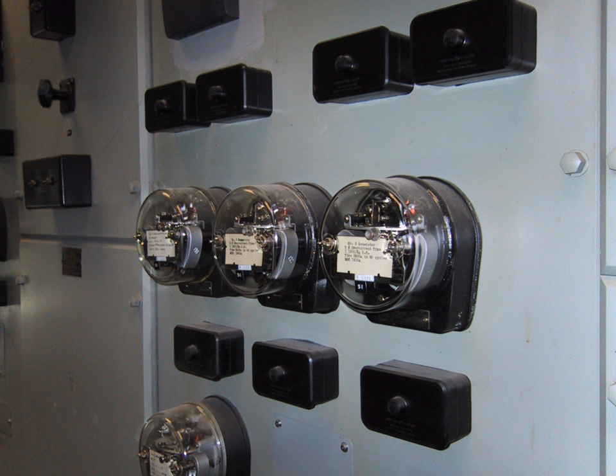Important transmission lines and generators have cubicles dedicated to protection, with many individual electromechanical devices, or one or two microprocessor relays. The theory and application of these protective devices is an important part of the education of a power engineer who specializes in power system protection. The need to act quickly to protect circuits and equipment often requires protective relays to respond and trip a breaker within a few thousandths of a second. In some instances, these clearance times are prescribed in legislation or operating rules.